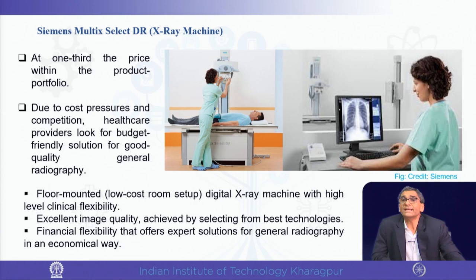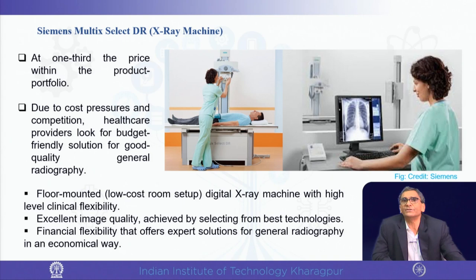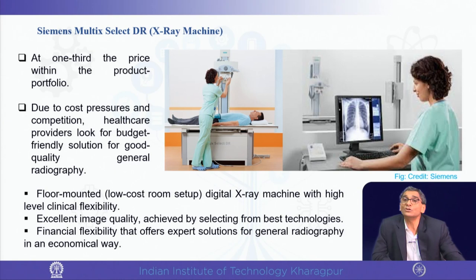Looking at X-ray machines: earlier, X-ray rooms required huge structural beams, making infrastructure costs very high. Instead, a floor-mounted device was developed that drastically reduced costs. With digital X-ray capability, high clinical flexibility, and excellent image quality, the total cost is reduced to one-third of the original.